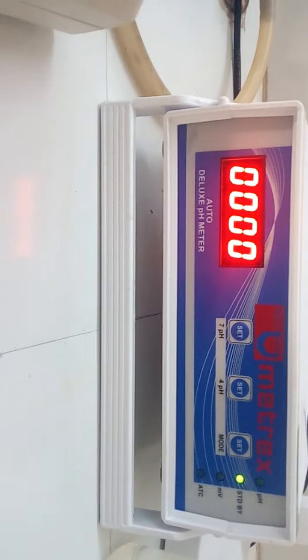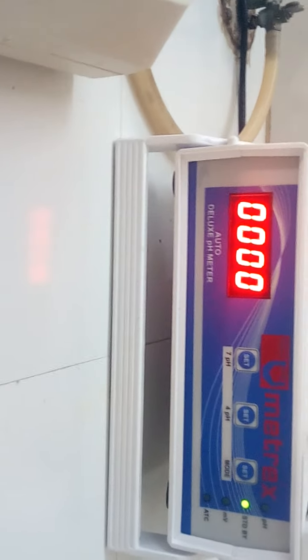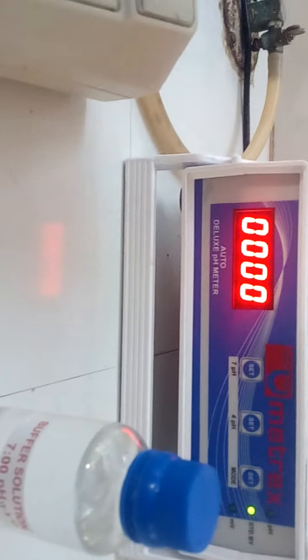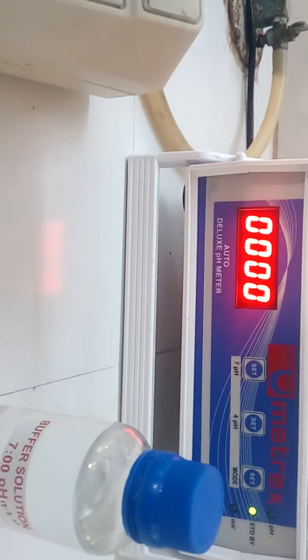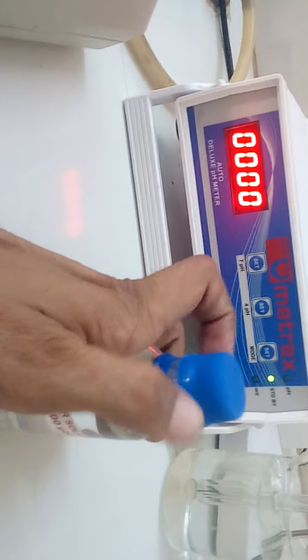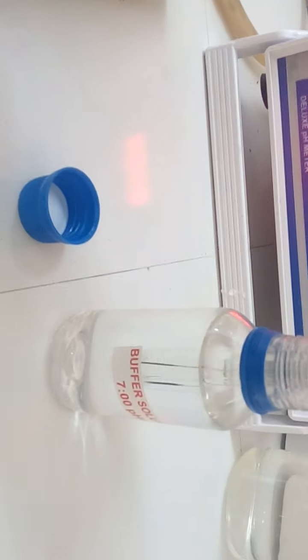During the calibration process, the 7 pH solution is used, which is required so that the instrument gives accurate results. Open the pH solution and dip the electrode in the pH buffer solution. After that, the pH electrode is cleaned with double distilled water and cleaned with a tissue paper roll.